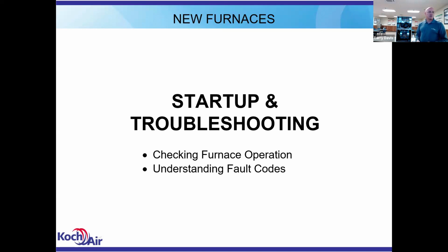A question came up: after you complete the changes on setting up the board, you scan the NFC again to save the changes. That is correct. You'll scan the board once, pull the information up from the board, make any changes you want to make, and tell the app that you're done making changes. It'll show you the list of the changes you've made. If that all looks good to you, you'll say okay, and it'll say scan the board again. You'll scan the board again, and you'll get a notification on your app that says download complete. And then you're done. Then you'll run the furnace and test it. So yes, you have to go back and scan it again to put that information back into the board.